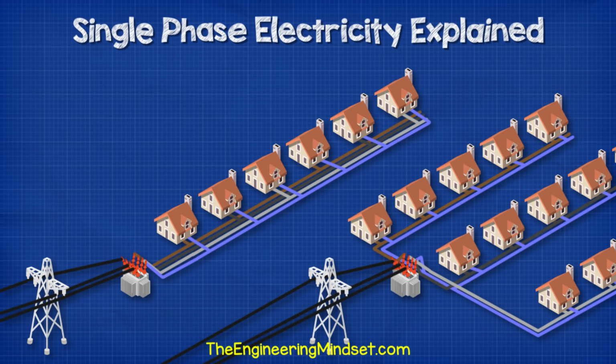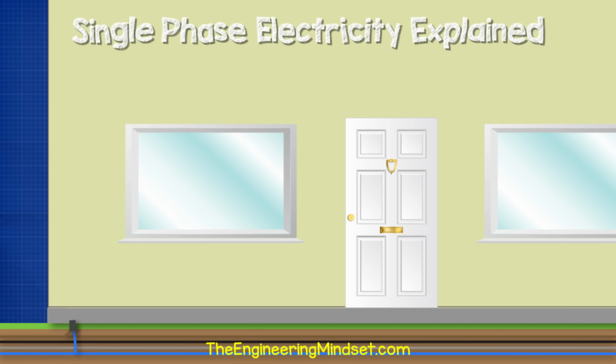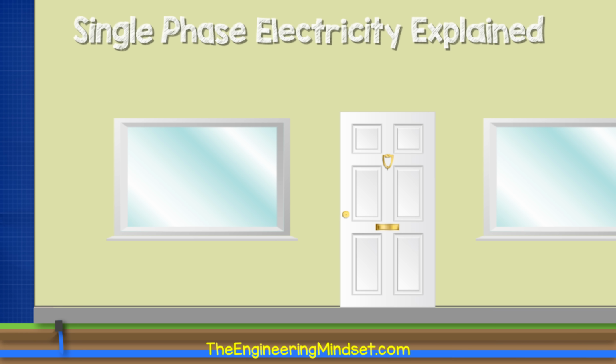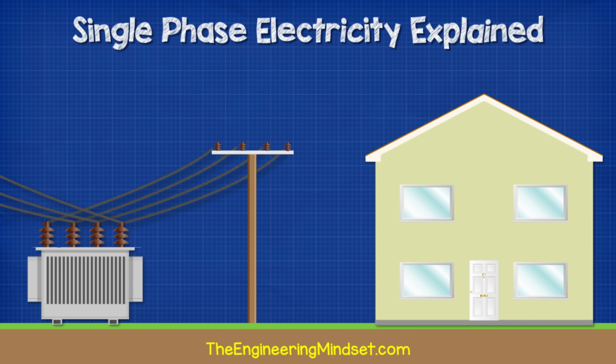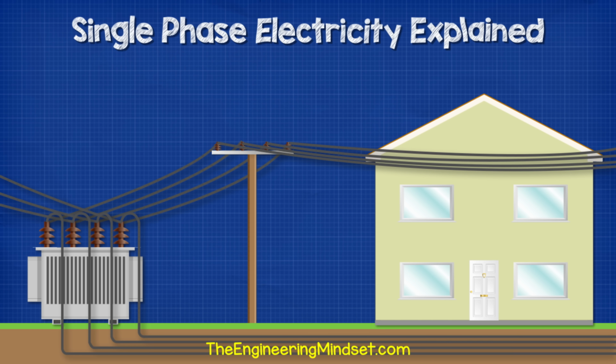We've also covered how 3-phase electricity works in a previous video, do check that out, links in the video description below. Now, each house in a street might be alternately connected to a different phase, or different streets might be connected to different phases. This is just to try and balance the demand on the transformer. A smaller service cable comes off the distribution cable and will feed the property. This service cable will again be overhead or underground depending on the local installation.